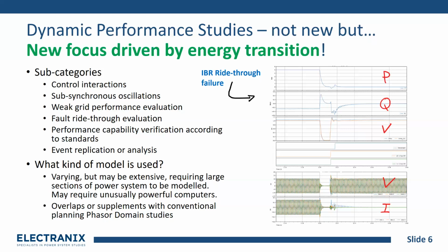On the right side, I've got an example of what that looks like when you're modeling a big system or a big region of a power system with lots of IBRs. You're concerned if these things aren't riding through normal faults. You can see what that looks like in an EMT tool. Your active power drops off in the top plot. Reactive power does something during the fault and then goes to zero. The voltage is recovering normally. And then you've got some trip signals. And then, the trademark of an electromagnetic transient tool is you can see the phase voltages and the currents. So you can see what happened there. The plant didn't trip off until the fault cleared, and then there was some transient, and then the currents ring away and the plant is gone. So this is what we're looking at with these ride-through studies often.